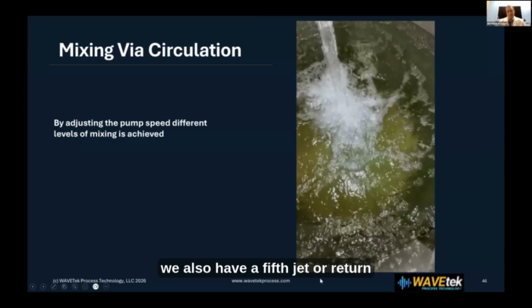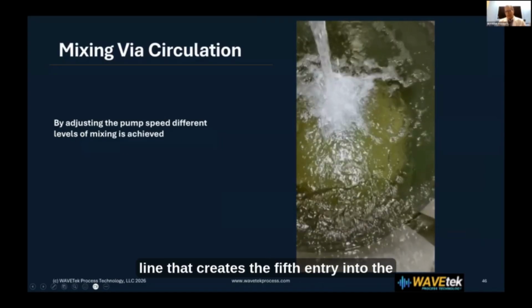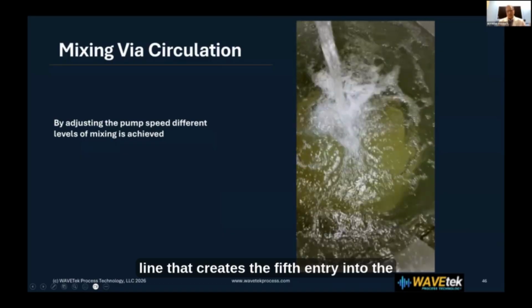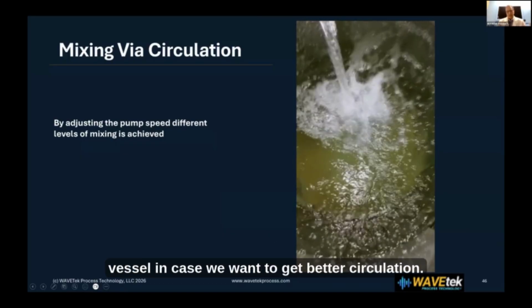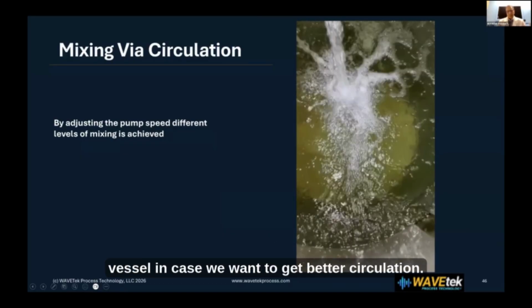We also have a fifth jet or return line that creates a fifth entry into the vessel in case we want better circulation. We've run numerous tests on these. In this case, we are at 80 degrees centigrade in the tank, and we can see the circulation lines are at about 73 degrees. These are not insulated at this time for demonstration purposes, but once they are installed in the plant, we'll have them insulated.